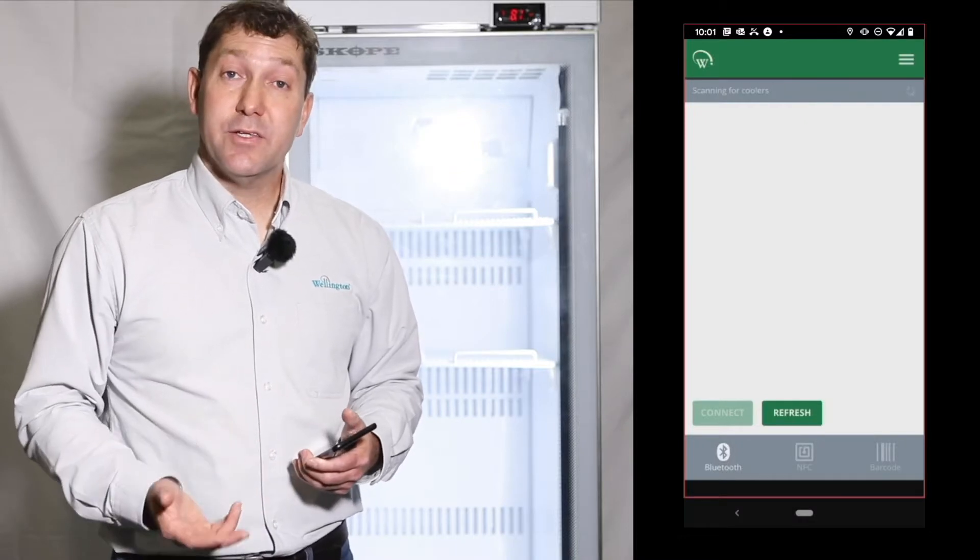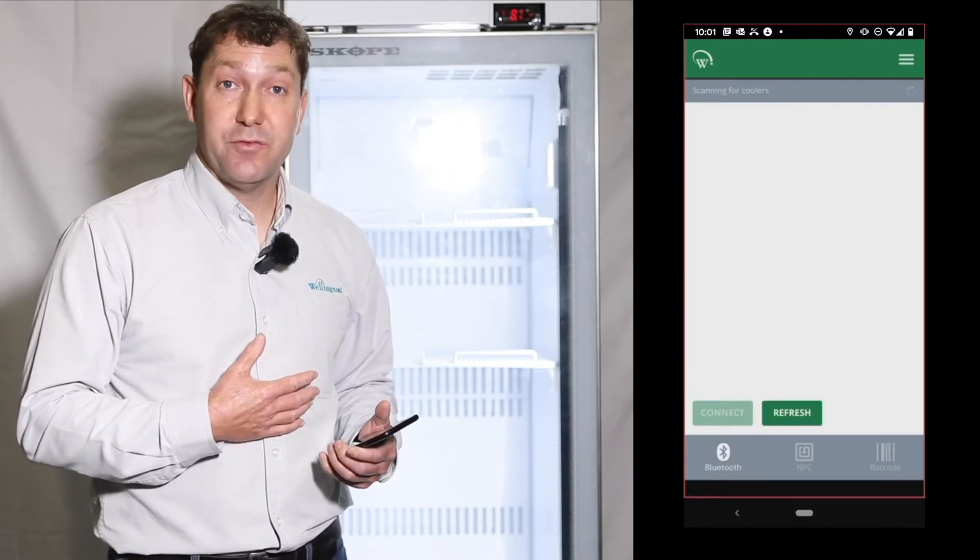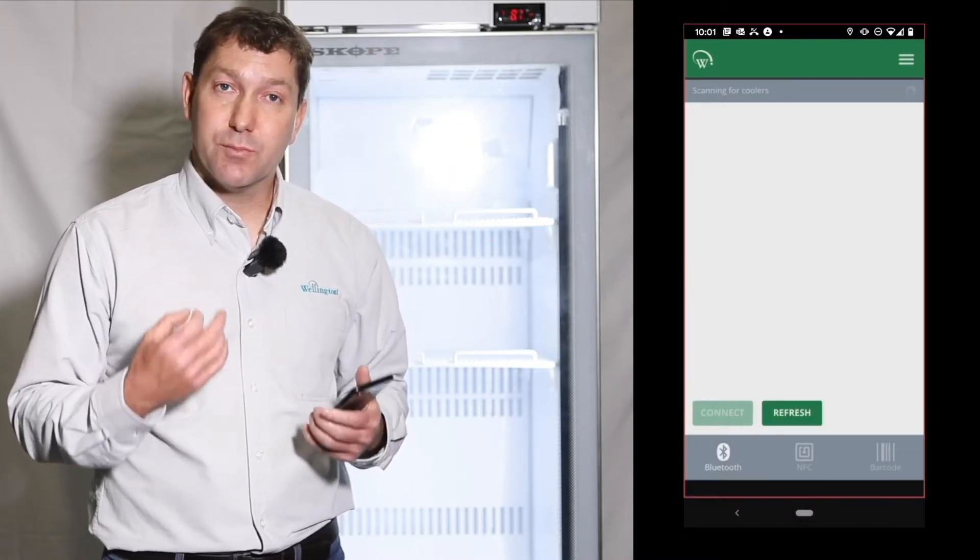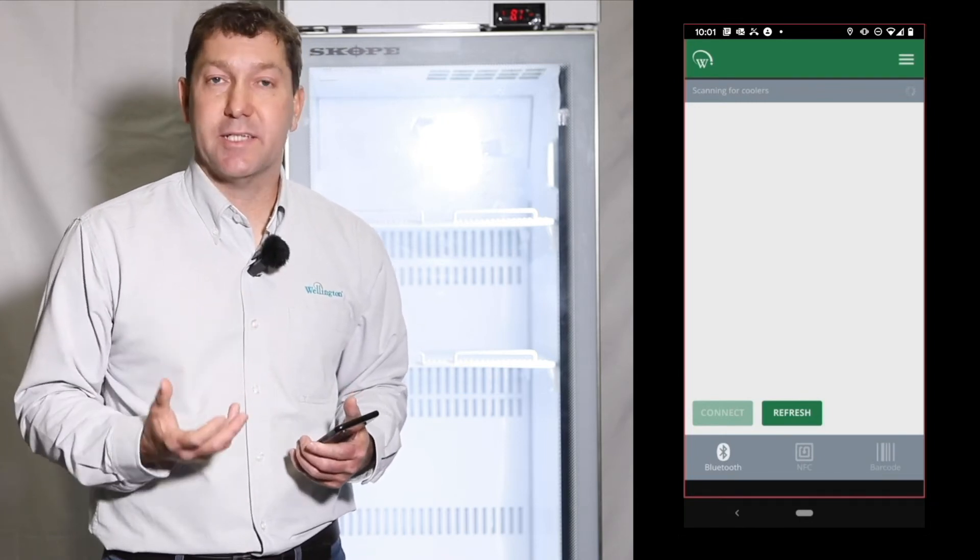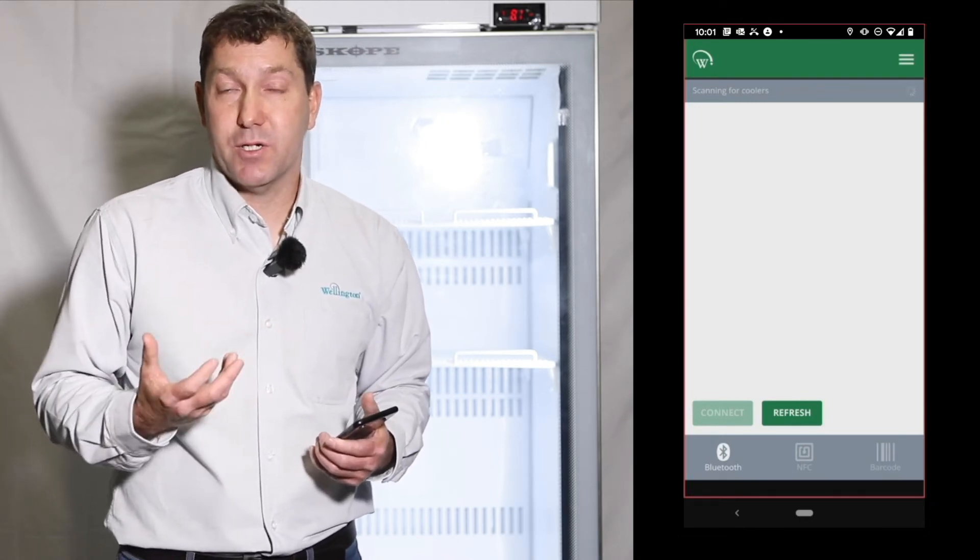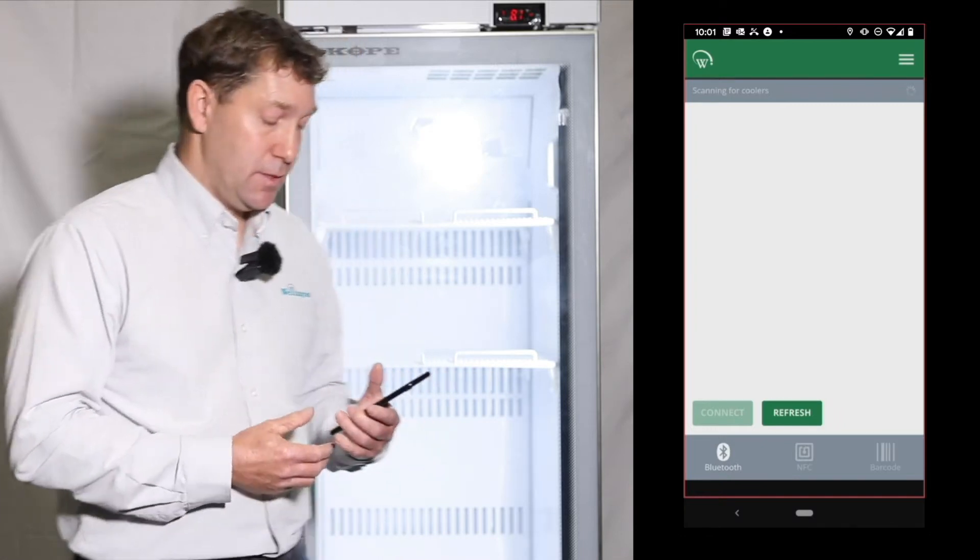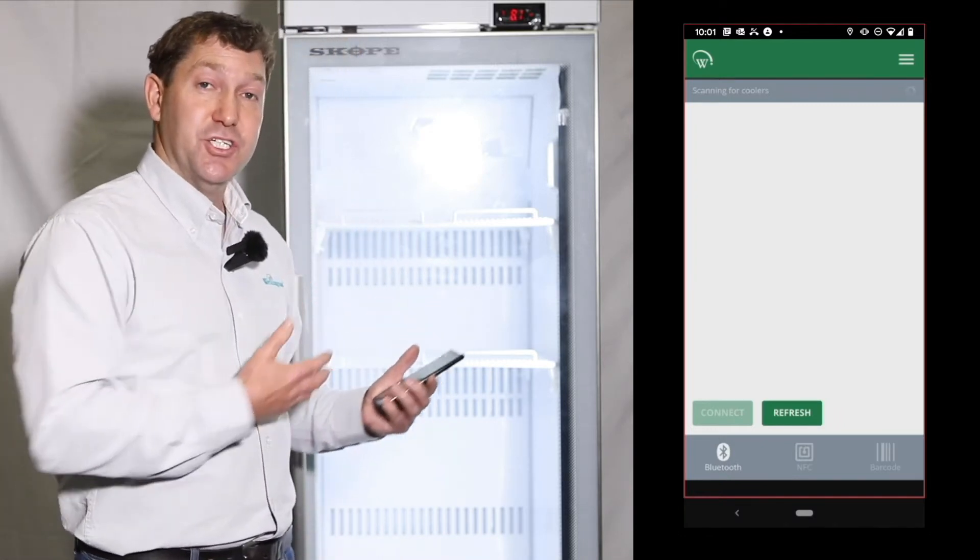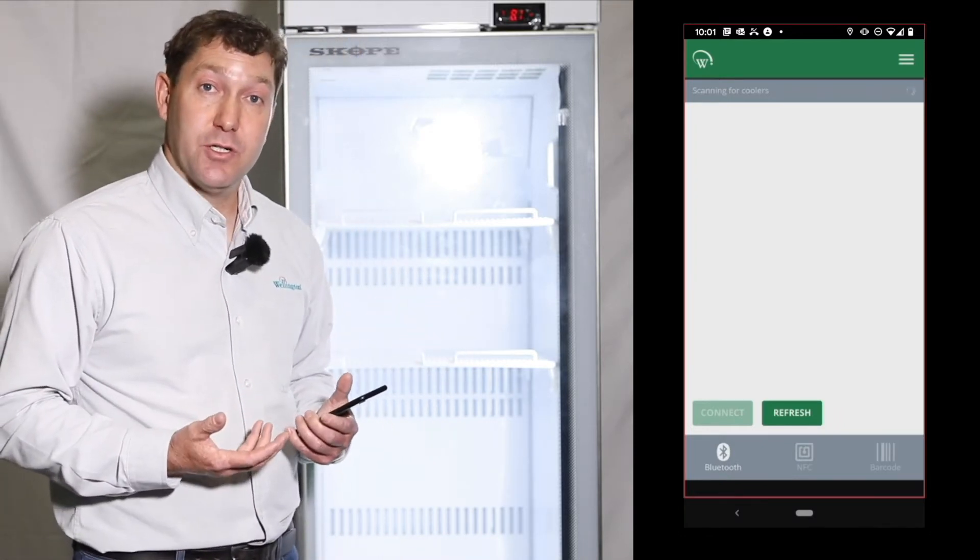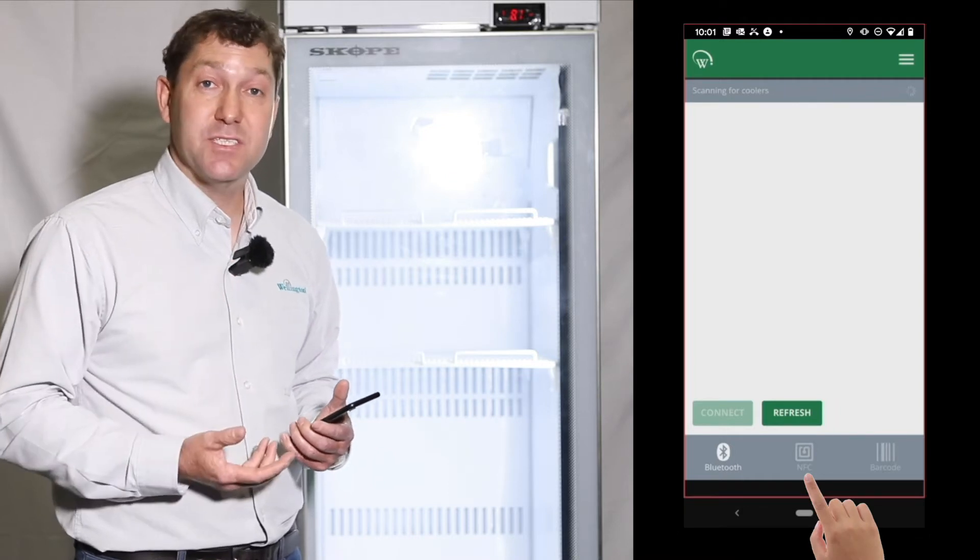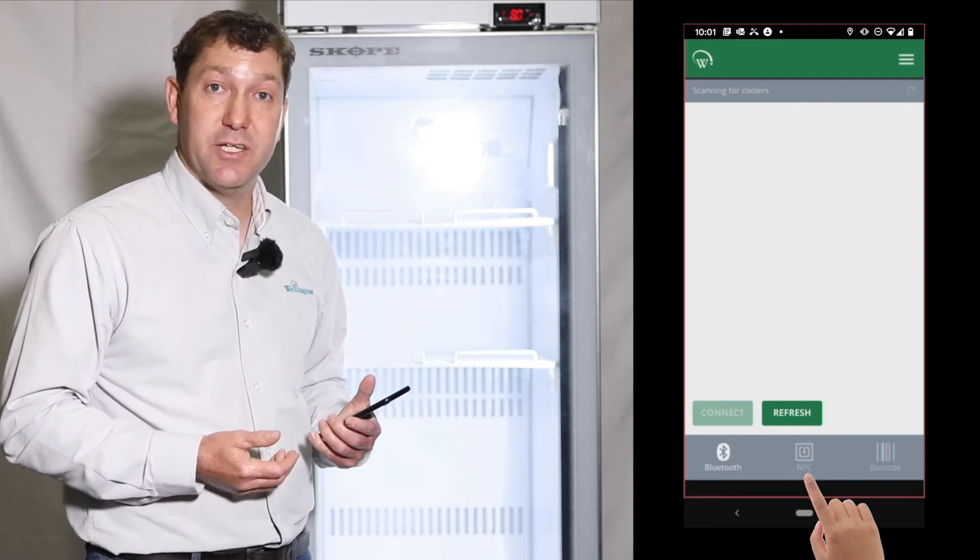Now that the Connect Monitor has been installed in the fridge, we now have to do just a small amount of setup so that it will connect to the database that the monitor is to be attached to. The monitor when it ships doesn't have Bluetooth turned on, and so therefore you need an NFC activated phone to initiate the Bluetooth.